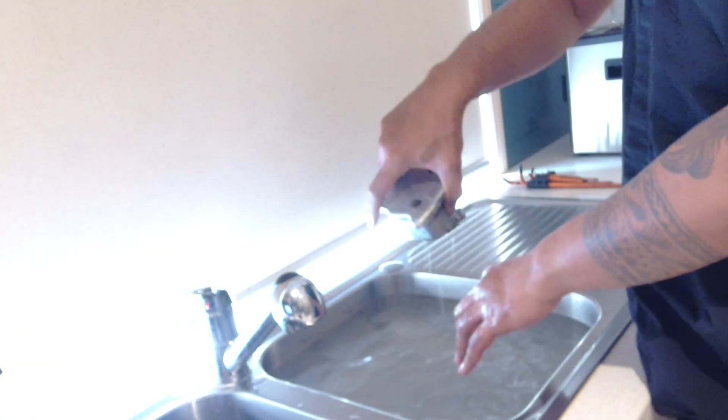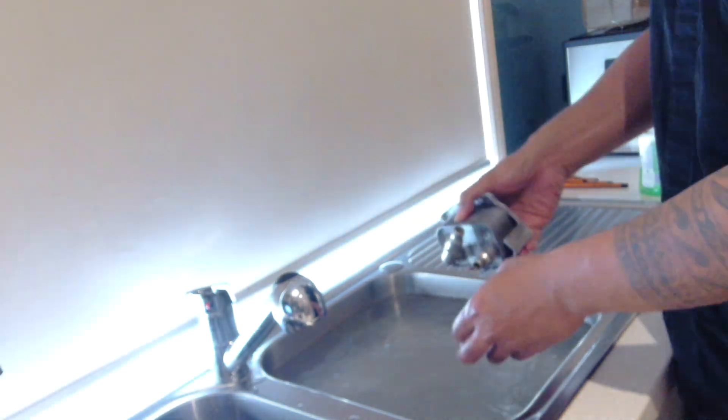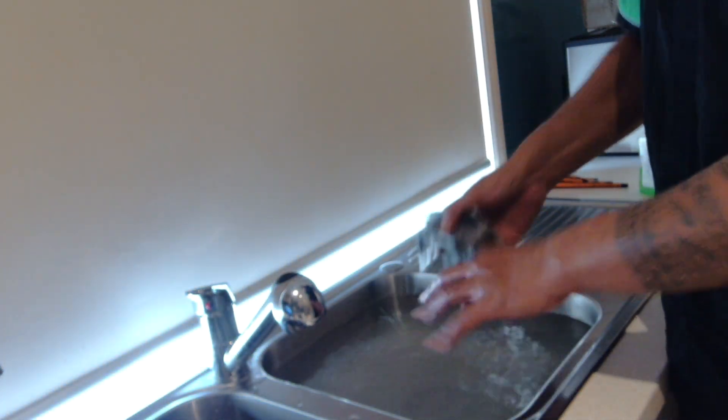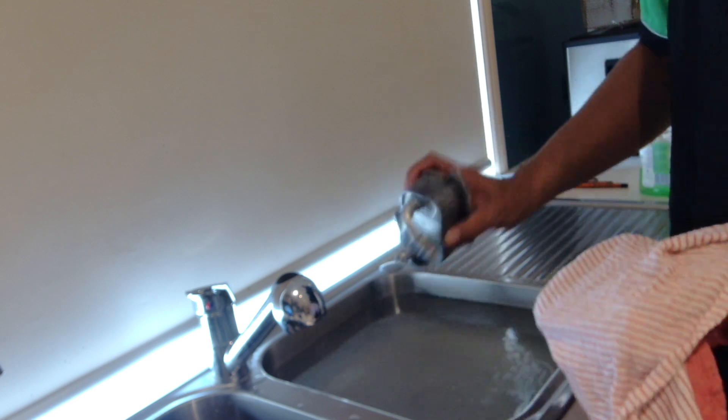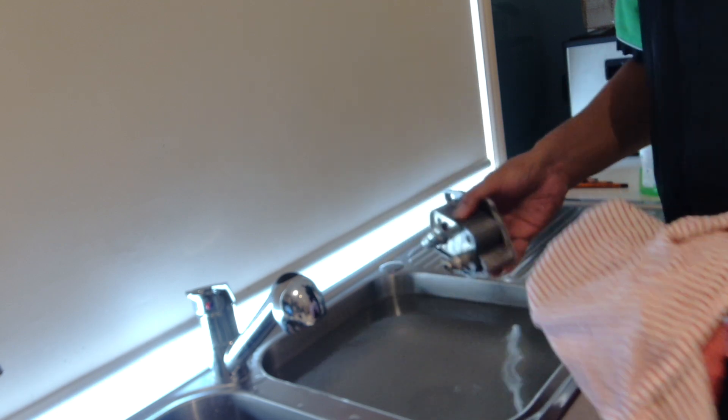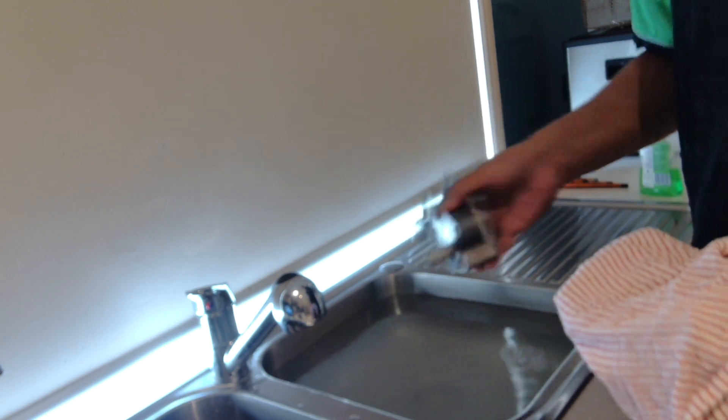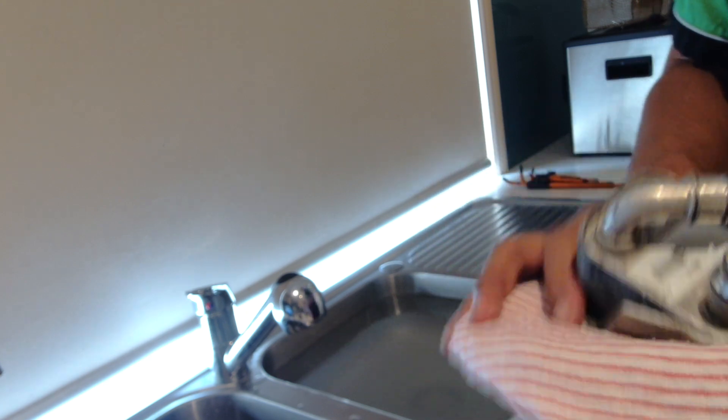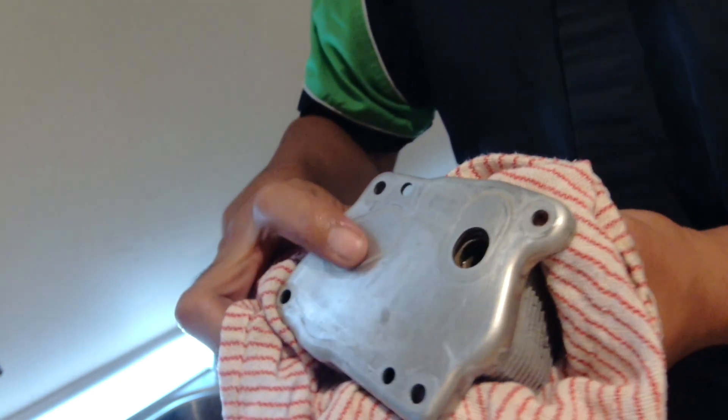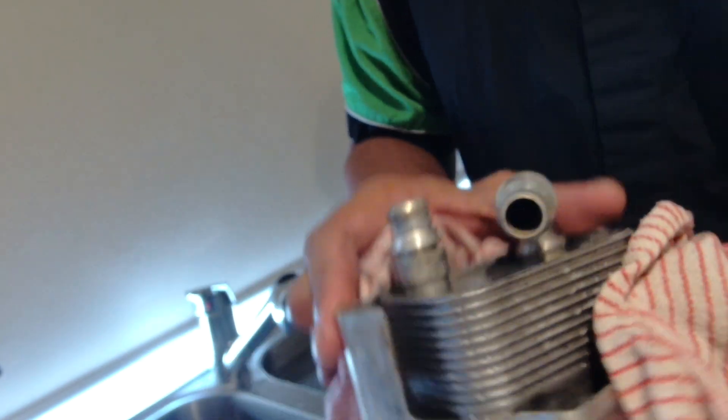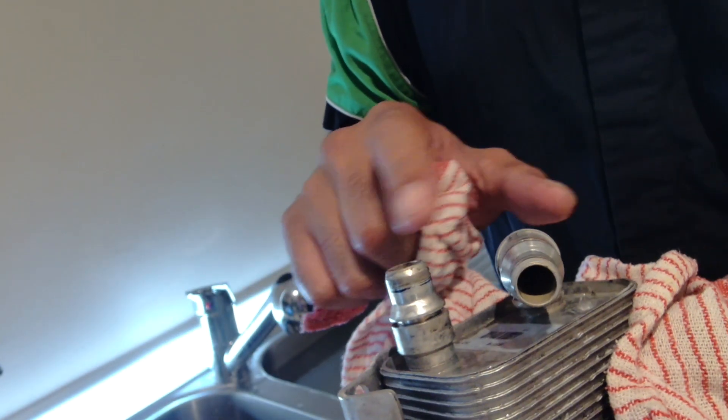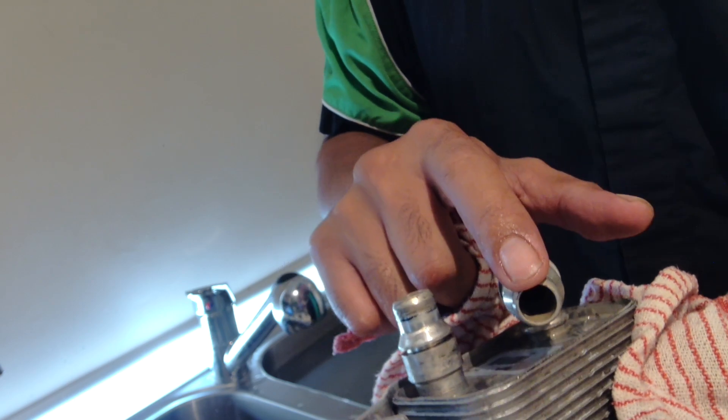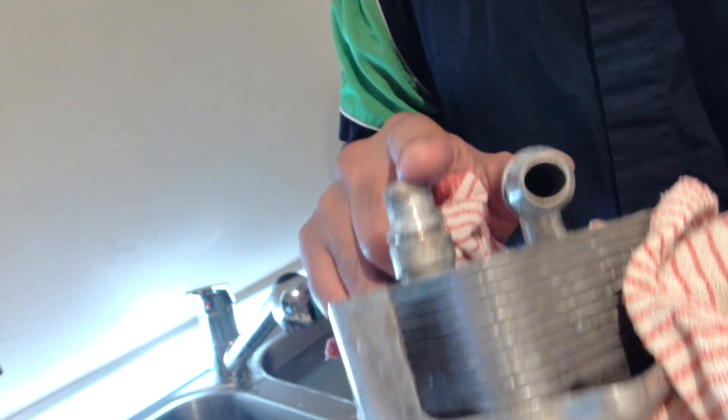So what I can tell you is that there is a breach in these plates, and this exchanger here is faulty and there is nothing you can do to repair it. When I was blowing into this hole here and blocking one, bubbles were coming out of here, out of both sides.